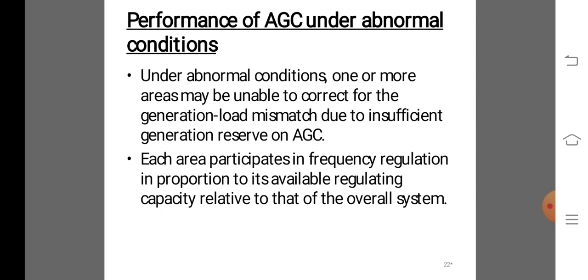This is the performance of AGC under abnormal conditions. Under abnormal conditions, one or more areas may be unable to correct for the generation-load mismatch due to insufficient generation reserve on AGC. Each area participates in frequency regulation in proportion to its available regulating capacity relative to that of the overall system. For interconnected operation, incremental efficiency, fuel cost, water availability, generation limits, tie-line capacities, spinning reserve locations, and area commitments are important considerations when preparing load dispatch schedules.